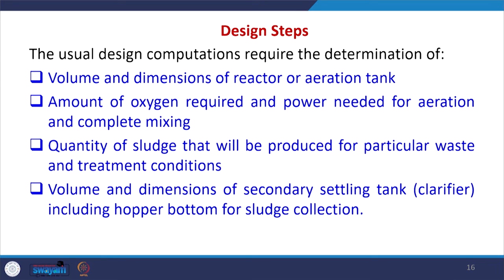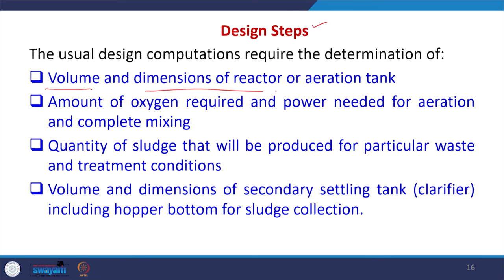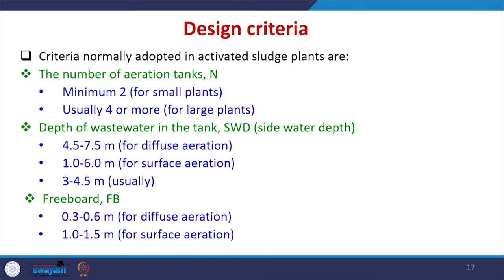The usual design computations require determination of: the volume and dimensions of the reactor or aeration tank; the amount of oxygen required and the power needed for aeration and complete mixing; the quantity of sludge that will be produced for particular waste and treatment conditions; and the volume and dimensions of the secondary settling tank or clarifier, including the hopper bottom for sludge collection.